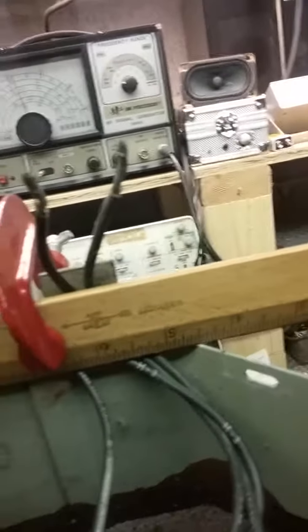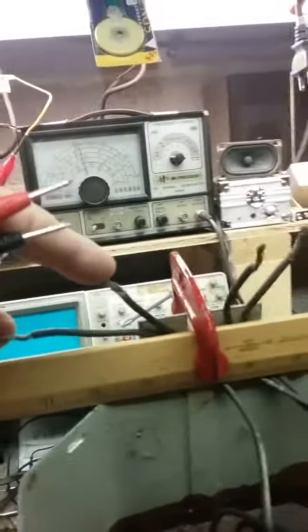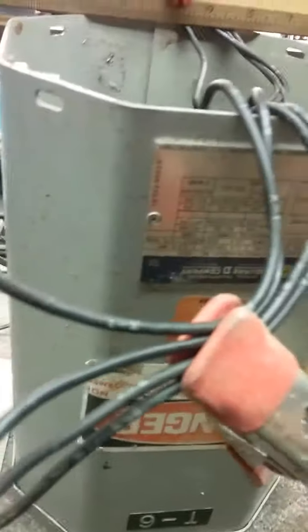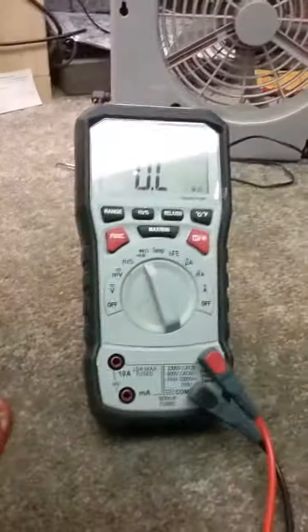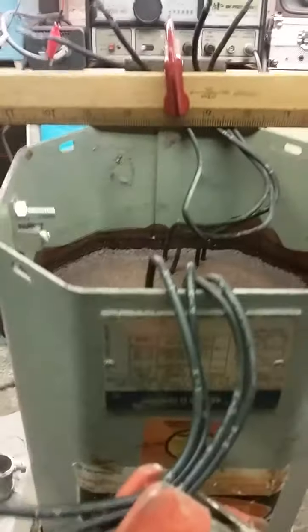So we're going to check the resistance. This is the primary first coil here, primary second coil here, secondary first coil is here, secondary second coil is here. And we will connect them up to my voltmeter here, and we'll check the voltage. They should be the same on both primaries, and probably close to half as much on both secondaries.